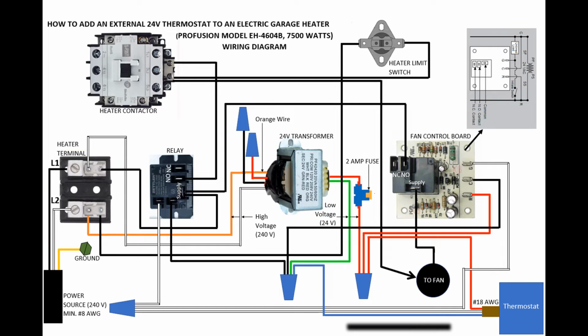So our contactor is a 240 volt contactor, and in order for us to turn it on, we need a high voltage relay to turn the contactor on and off. A relay here, we have 3 high voltage terminals located here. I've labeled them as supply, normally closed or NC, and normally open or NO. The NO and NC refer to the communication of these terminals with the supply voltage. And high voltage is supplied to this terminal as shown in this black wire. We have a wire going from L1 to the supply terminal. So you can see the contactor is connected to NO terminal of the relay with this black wire. NO refers to as there being no continuity when in normal position. Basically, the circuit is open, meaning no current is flowing through it.